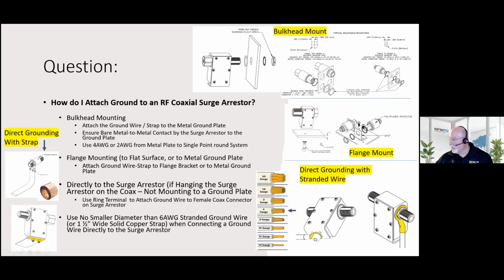If you're just hanging it, then use a ring terminal, either for the end connector, or this model has a little threaded insert and we provide that bolt. So you would attach your ground there. And again, use the 6 gauge stranded. You can also use the 1.5 inch strap using a certain little gadget we provide.